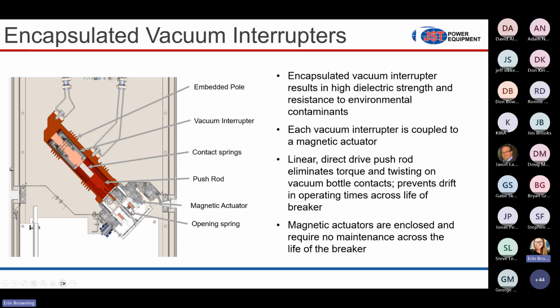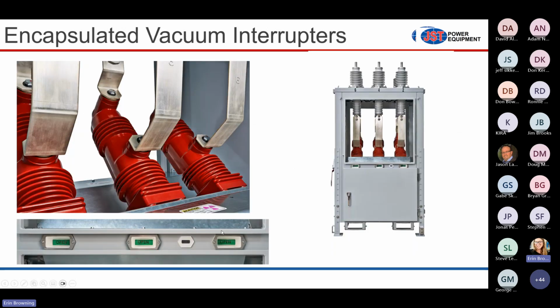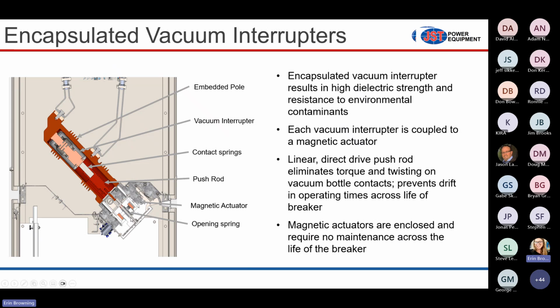The actuator down here at the bottom moves up and down. It's a linear direct drive motion. There's no crankshaft, there are no rotating components. It is a shaft that physically just moves up and down in between the circular shaped magnetic actuator. When it moves up and down, it's directly coupled to this push arm, and this push arm moves the bottom contact up and down to open and close the vacuum bottle. So it's a very simple device. Again, there's absolutely no maintenance required on the actuator itself. It's enclosed. I have another image of it that I'll show you in a moment. But absolutely no maintenance required on this actuator.